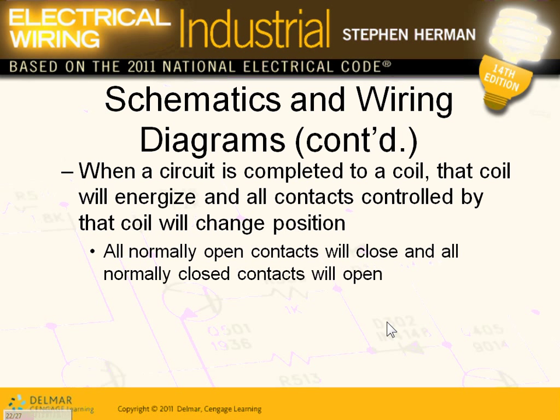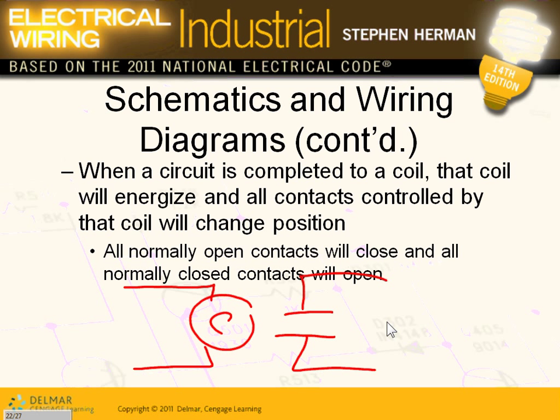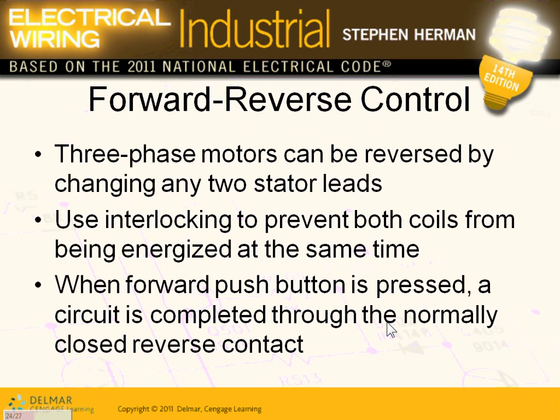When you energize a coil, that coil is driving a contact. When you bring 120 volts across this coil and energize it — this contact is normally open — what's going to happen? This contact is going to close. When you energize a coil, the coil will physically and mechanically drive the contacts to close. That's how that works.